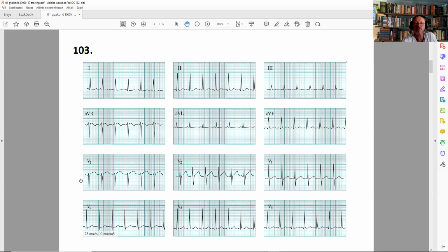Lead number 3 is located at 120, so you have to count back 90. It means that you have 30 or you have 210. Now you can go for AVR, because that's 210. Whether it's positive or negative, that's negative, so this is around 30. However, lead number 3 is still positive, which means this is more than 30.